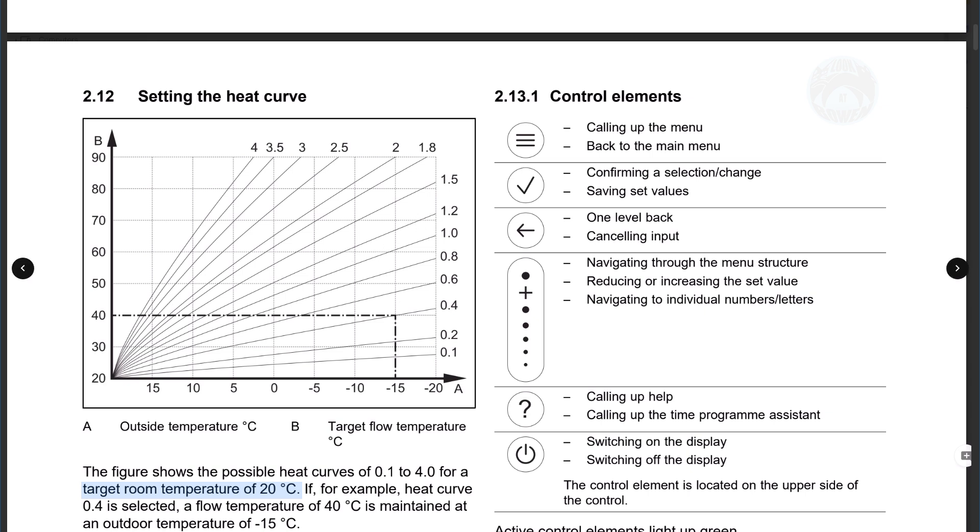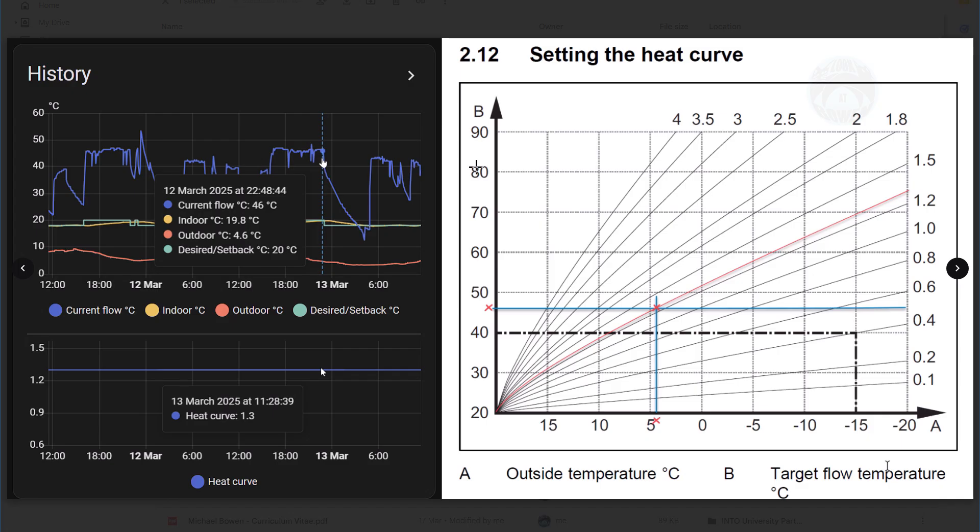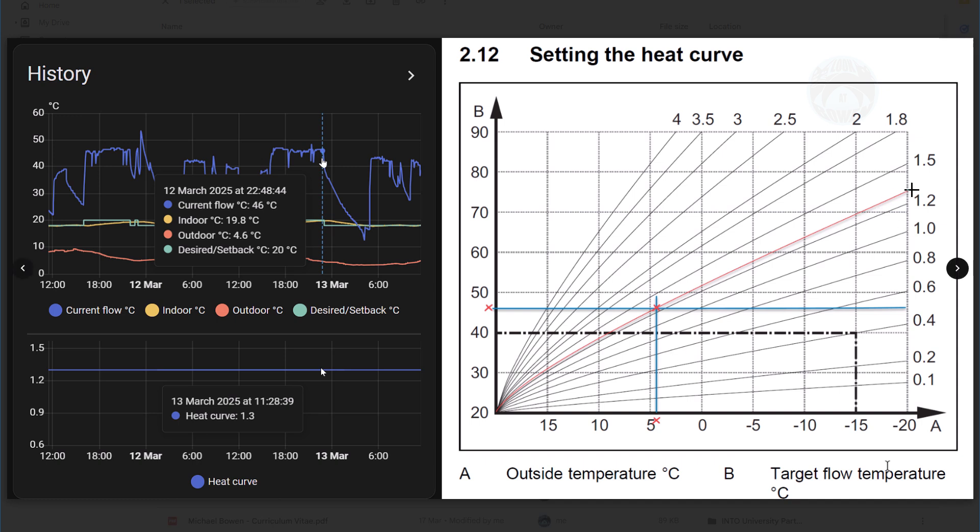And this then really started to help a lot because now I was able to nail down the heat curve that I needed to be on. Now, I wanted to be on 1.3. So what I did was I created a 1.3 line and I've assumed it's around about this position and I've placed it. Now, obviously, the target temperature is 20. And then I picked that heat curve of 1.3 and I watched it over a period of a couple of days.